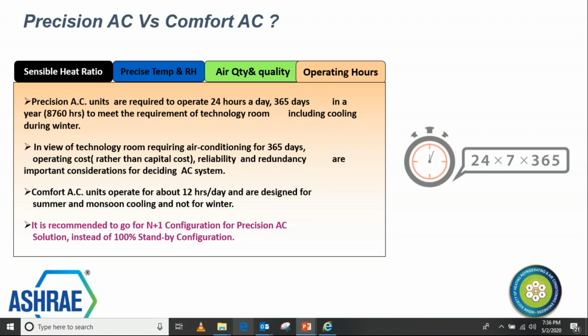In comfort units, most of the time we see plastic or composite material used, and we also see the components selected are of a different grade. We see a lot of normal fans used there, compared to precision AC, where only a few selected suppliers and the global best suppliers are used for the components. So it makes a lot of difference at every component level, which makes it work for the 8760 hours continuously. And this also ensures that the redundancy level is provided here, because precision ACs have a high lifespan and, I would say, better MTBF and MTTR. If you compare each and every component's failure hours to comfort, it is much lower.